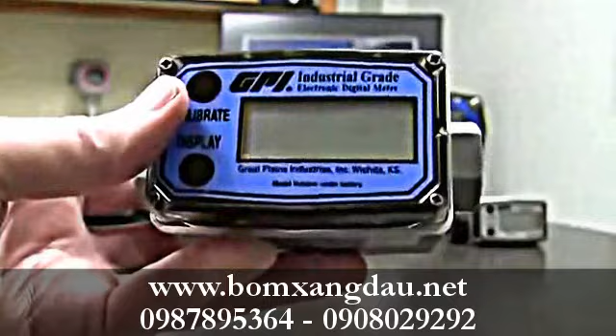So what we do in a field calibration is show this display exactly what 5 gallons looks like. Now I'm using 5 gallons as an example, but you could use any amount that you want, 10, 15, 6.29, whatever it takes. A lot of people will do it with weight, so they'll know exactly how much their fluid weighs, and then they'll fill up a container, measure the weight, figure out exactly how much they put through the meter, and then enter that into the display. That's why I say it can be any amount, 6.57, whatever it takes, put it in there right.